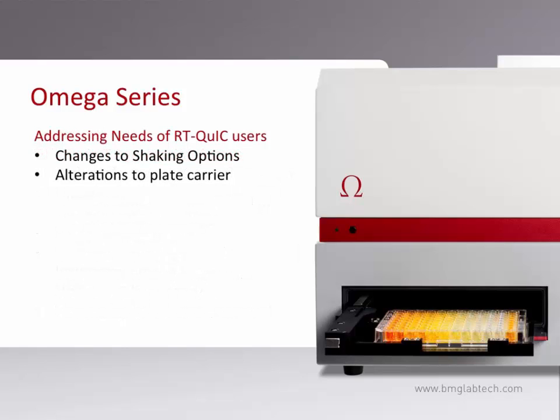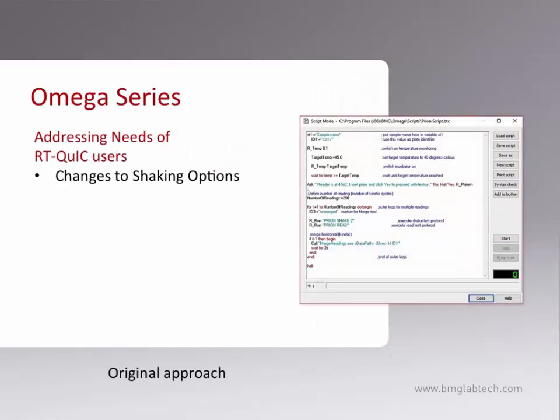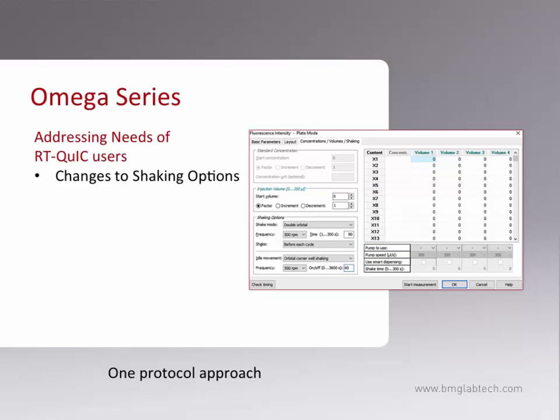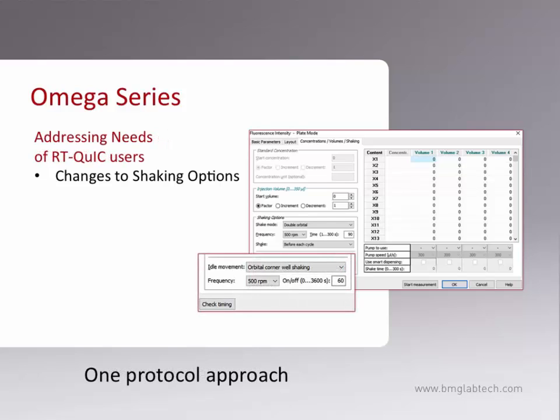As it became apparent to BMG that the RT-QUIC assay was very important among a segment of our customers, we sought their input as to how we might improve. When the RT-QUIC assay was originally designed, achieving the required shaking required a protocol distinct from that used to detect thioflavin T signal, and these two protocols were run repeatedly using BMG's scripting capability. Although the script approach was extremely successful, we thought it would be better if it was not required. To make a one-protocol approach possible, we changed the shaking capabilities so you can now perform a shaking action whenever the plate is not being read. The shaking can be constant or cycled on and off.